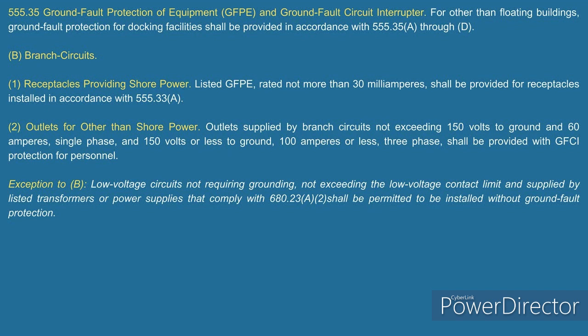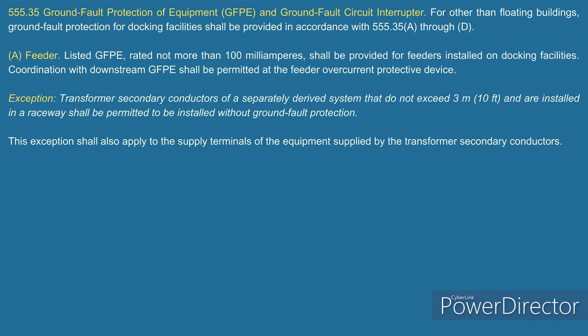Okay. And it says, if I'm going to shore power, it says listed ground fault protection of equipment not rated more than 30 milliamperes shall be provided for receptacles and installed in accordance with 555.33(A). And that's where if you already provided upstream with a feeder, you're okay, right? And then you can dial it down to whatever you need to match it. And if I go back and look at 555.35(A), it says it will not be rated more than what? 100 milliamp. So that ties into what you were just saying.